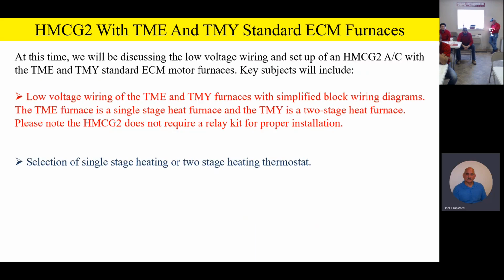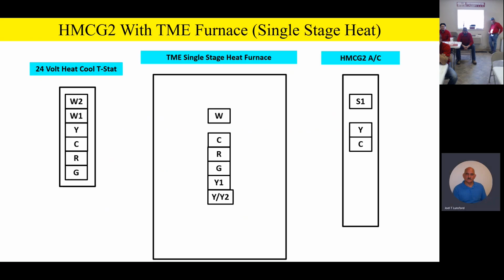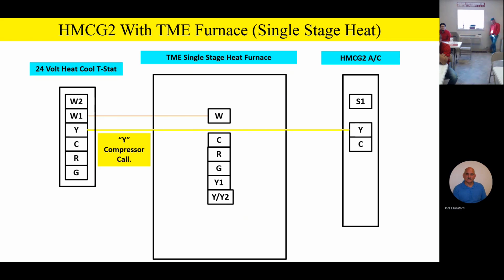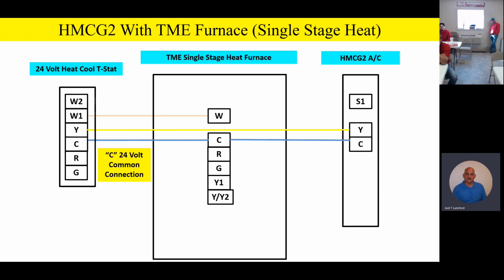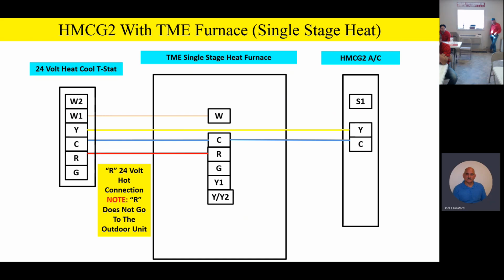So if we look at a TME and a TMY furnace, it's going to be essentially the exact same wiring we had before, except the terminals are going to look a little bit different. We're going to have a W terminal on a TME because it's single stage. Yellow goes all the way outside like we did before. 24-volt common goes all the way through. R terminal is 24-volt hot.